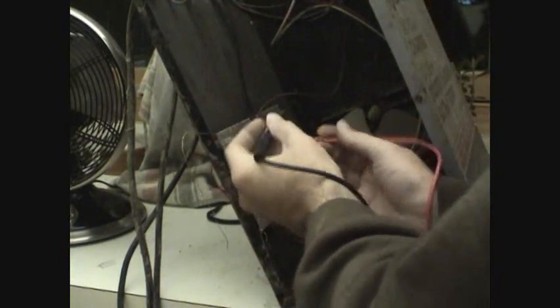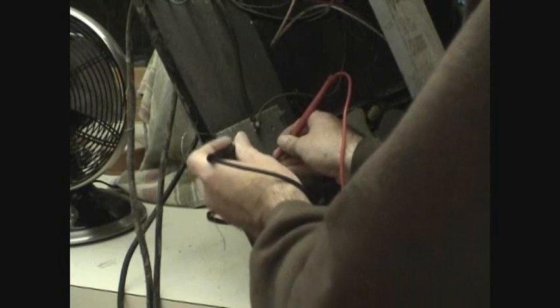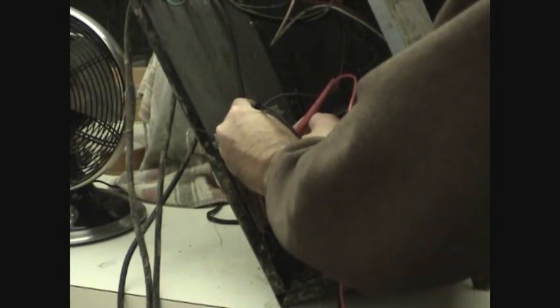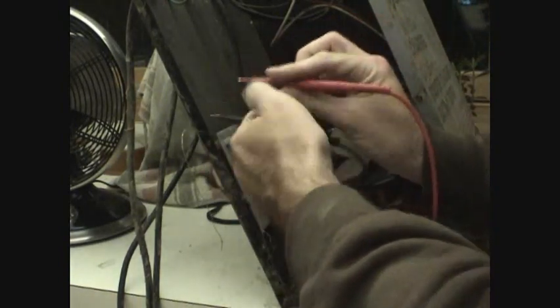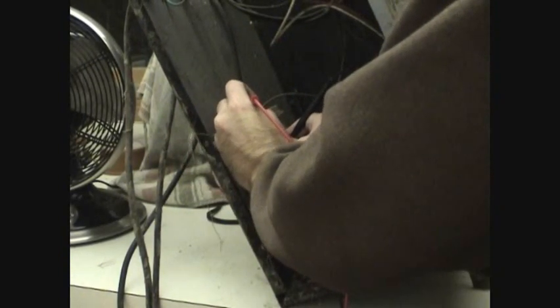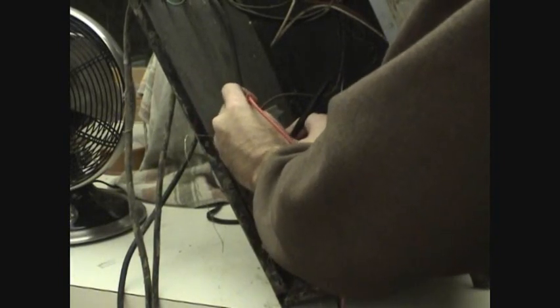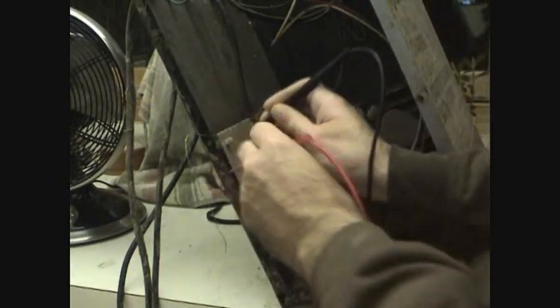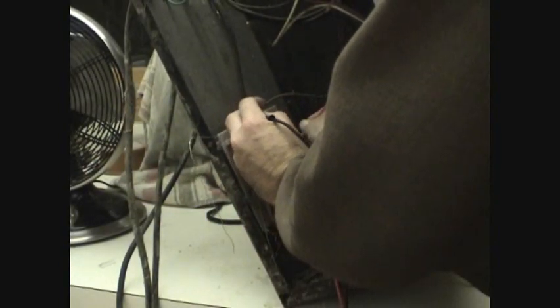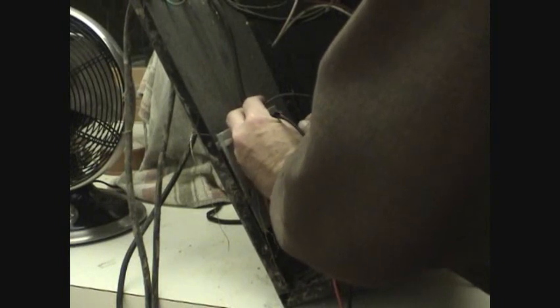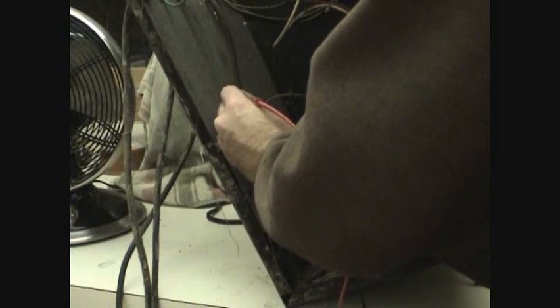Kind of cramped in here. So no continuity there. We'll reverse our leads. No continuity there. So at a minimum we already know we have one bad rectifier. We'll reverse the leads once more and go to the second rectifier. No continuity, which I would expect because this is the positive side. I'm having to press on these really hard because everything's so dirty. And no continuity there, so we know our rectifiers are open circuit.